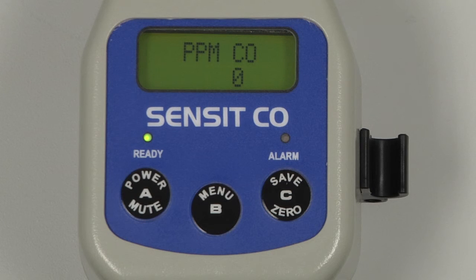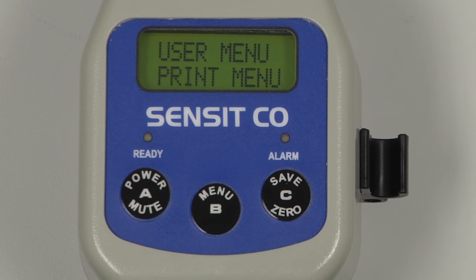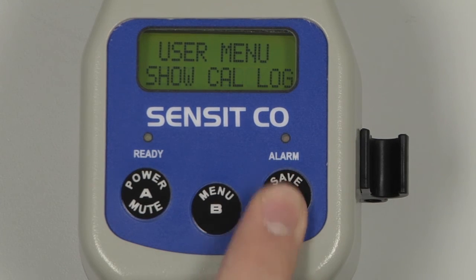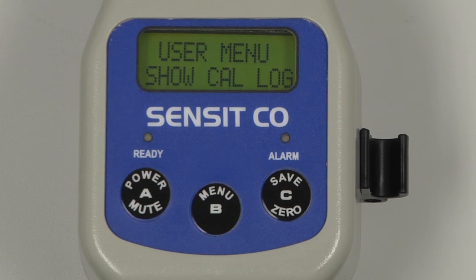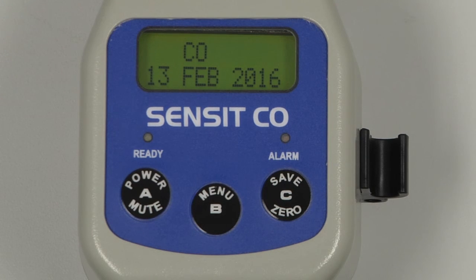To verify the calibration date of the instrument, enter into the user menu by pressing and holding the B button and scroll by pressing and releasing the C button until 'Show Cal Log' appears. Select by pressing and releasing the B button, and on the screen will be displayed the most recent date that each sensor was calibrated.